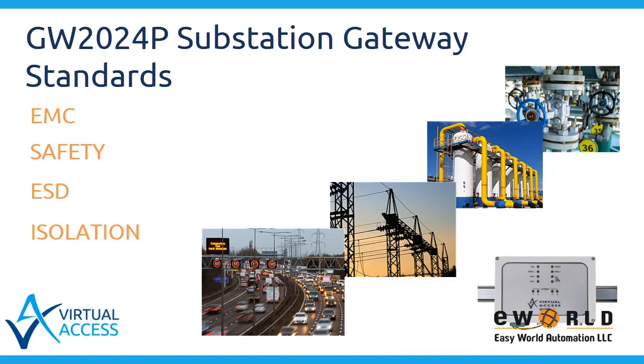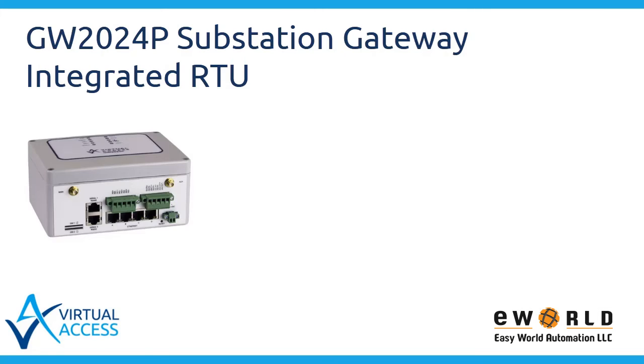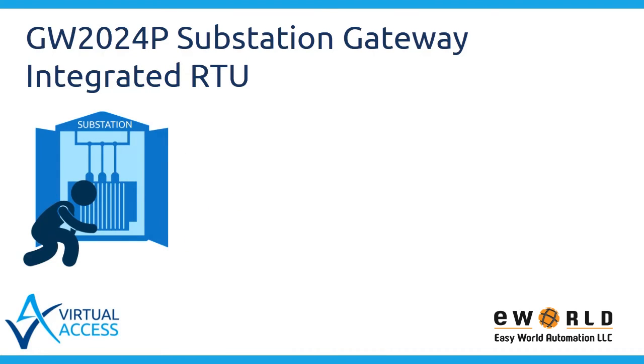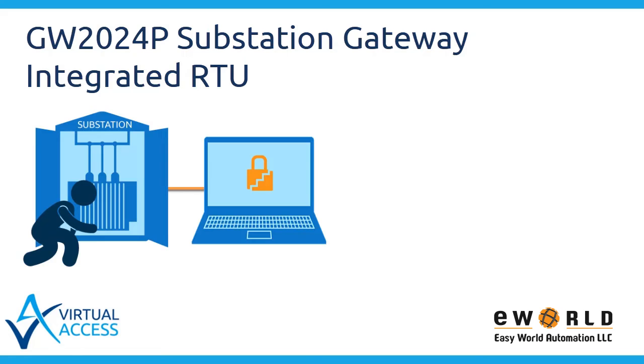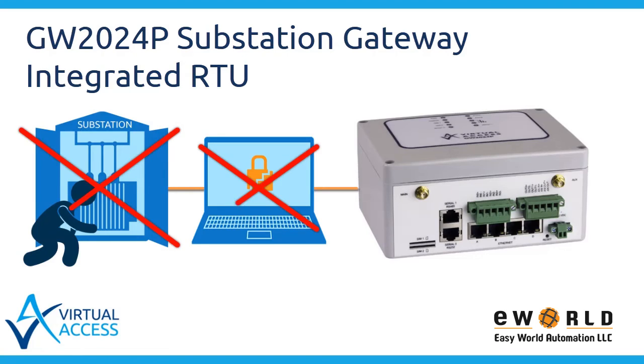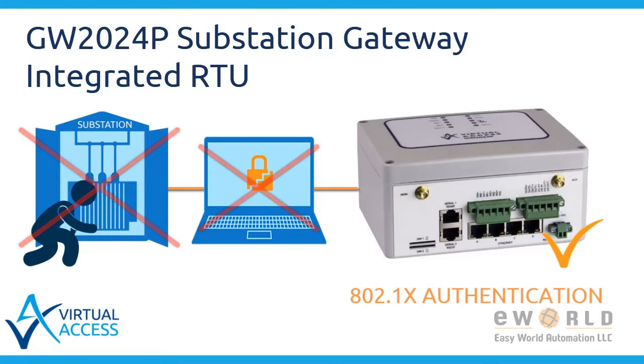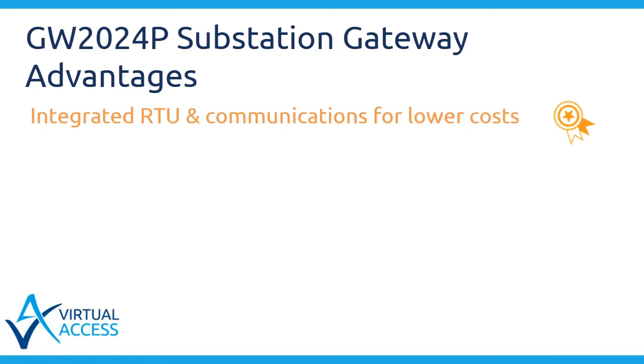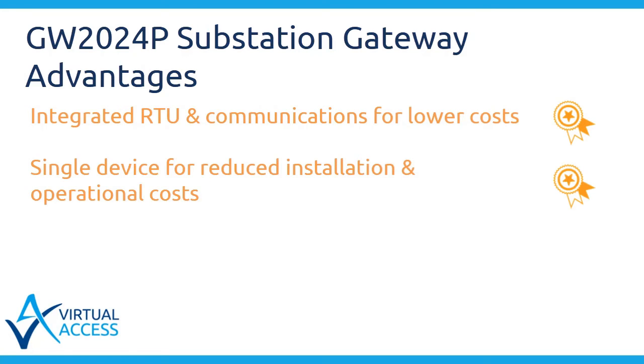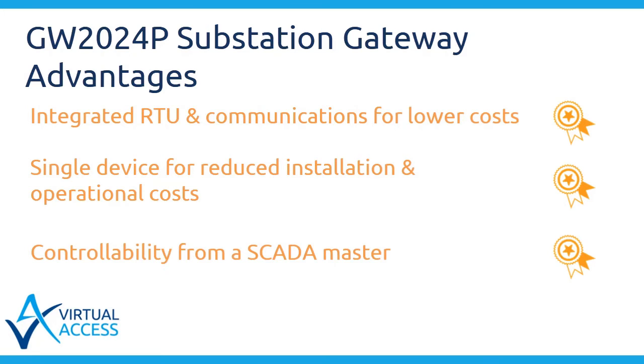Its PVC enclosure enables the GW2024P Substation Gateway to be electrically isolated from ground, providing a high level of immunity from electrical surges. RTU functionality is integrated into the device, allowing increased security. For example, in a typical cabinet, the cabinet door could be forced open, the Ethernet cable disconnected from the communications devices, and the RTU connected to a local console that could control the RMU switching. In the GW2024P Substation Gateway, the RTU is integrated with communications and it has an 802.1x authentication, so this scenario would be highly unlikely. Other advantages include integrated RTU and communications for lower cost, a single device for reduced installation and operational costs, and controllability from a SCADA master.